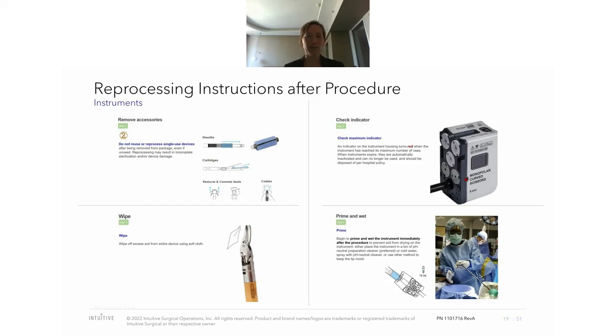And actually, that prime and wet step is one of the most critical steps here as well. And you already see a syringe with 15 milliliters of liquid that can be water or an enzymatic neutral detergent that is going into flush port 1. And to give you a bit more information, flush port 1 is going directly into the shaft, and priming through flush port 1 with those 15 milliliters will basically fill up the shaft to ensure that it is staying moist until it can be reprocessed again in the CSSD department.